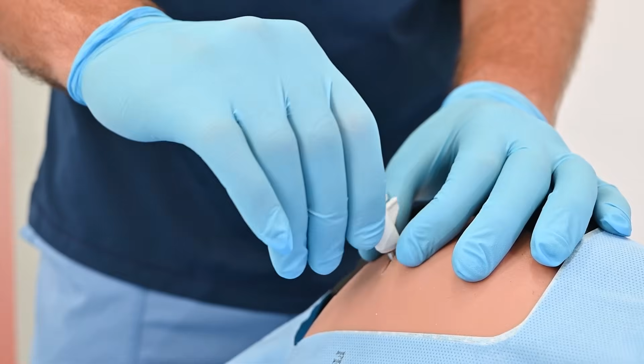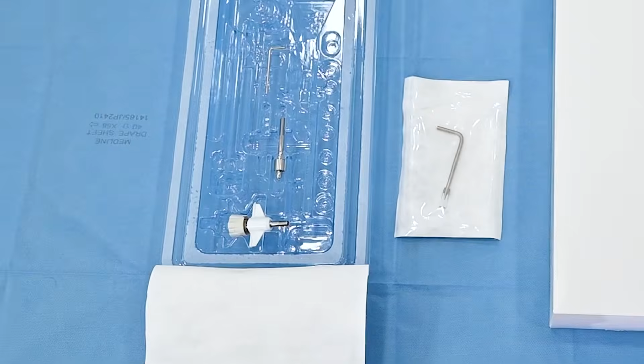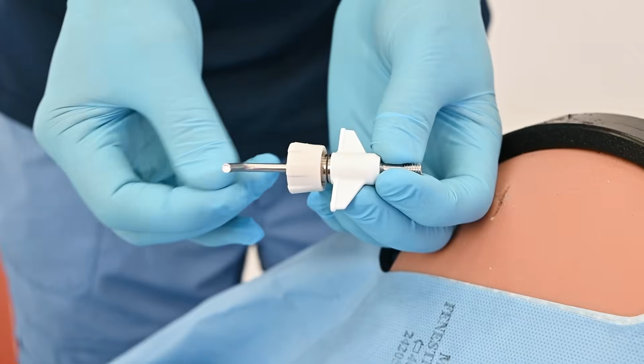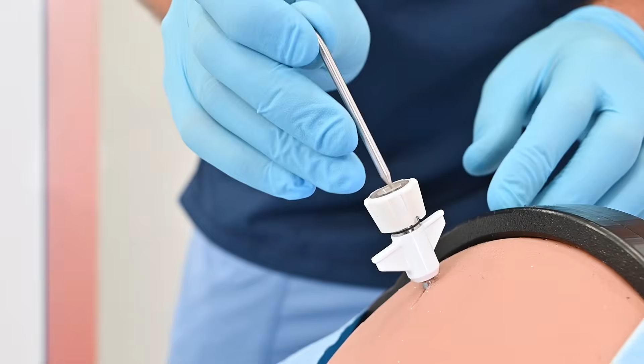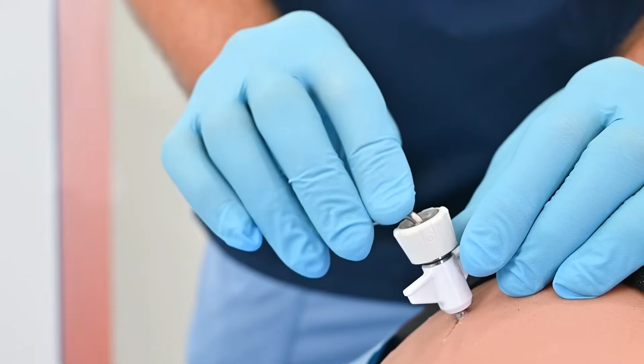Rotate the bolt clockwise to secure it into the skull. Each full rotation advances the bolt by 1 millimeter. Continue rotating until the threads are fully engaged and they are no longer visible below the skin, or until the bolt is securely fixed, whichever occurs first. Note that the bolt is pre-assembled with the cap loosened to allow catheter insertion. If the dura is not adequately punctured, the dura opener may be inserted through the bolt to pierce the dura.